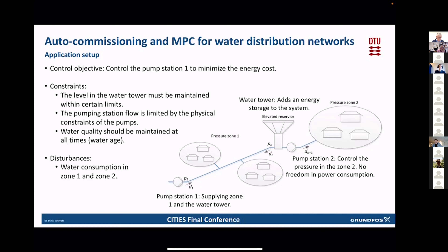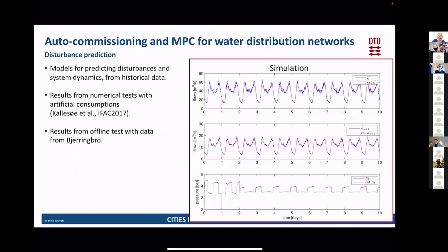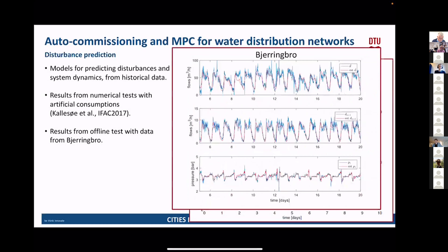The water tower is really our energy storage. However, we also have some constraints because we cannot overfill this water tower — the water will run over into the streets — but we cannot empty it too much either because there are requirements for firefighting. So there are lower limits on the water tower, and of course some limits on the pumping station. We also have some limits on water quality, and for a water tower that really means how is the average age of the water stored. So we have to continuously take care of exchanging the water in the water tower to ensure water quality.